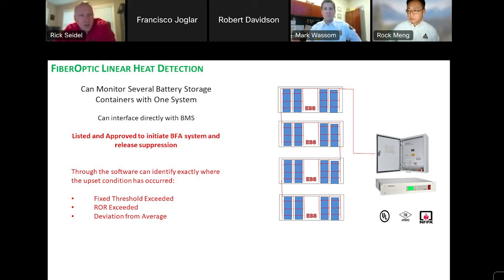Specific to energy storage system applications, you can monitor several units or containers with one system directly integrated with the BMS, and through the software, identify exactly where an upset condition has occurred. Alarm set points along the entire length of the cable are available and can be programmed as either a fixed threshold value, a rate of rise threshold, or deviation from average. These features make fiber optic linear heat detection a very viable means of localized monitoring in very tight areas or several areas next to each other, like these energy storage system containers typically end up at the site.